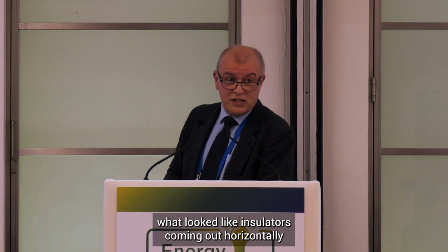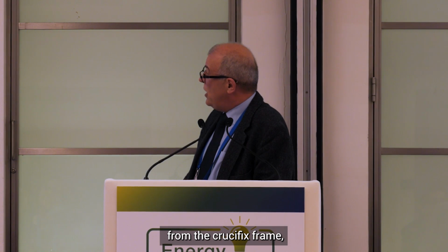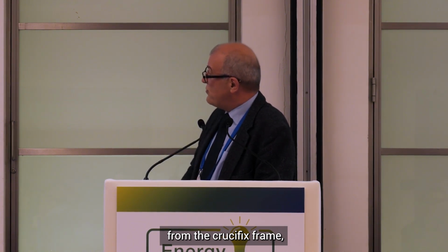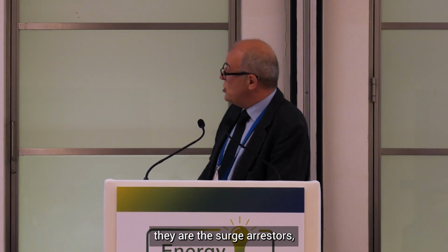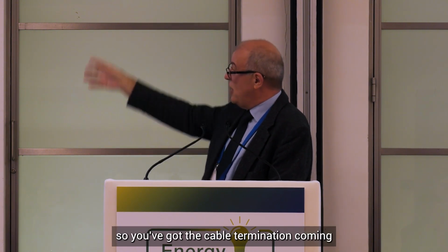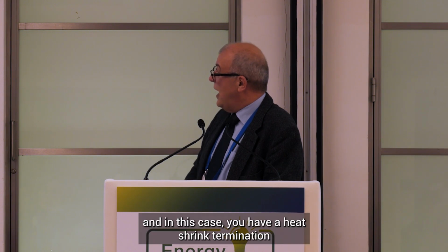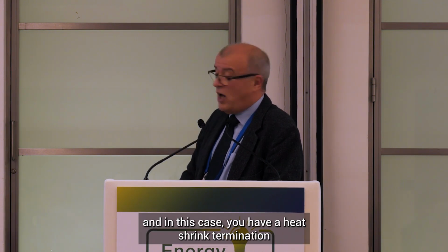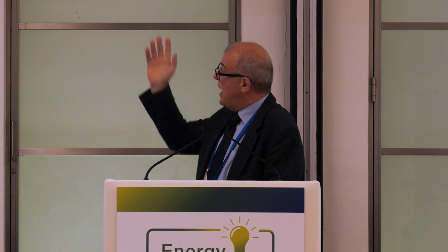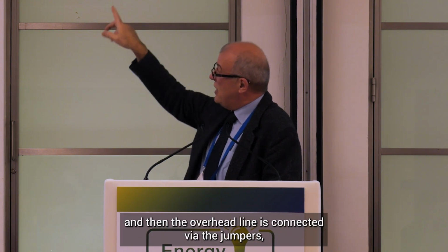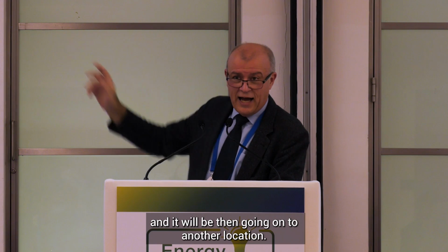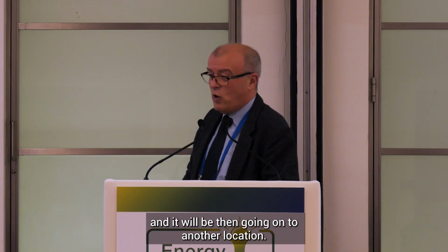what look like insulators coming out horizontally from the crucifix frame, they are the surge diverters. So you've got the cable termination coming up from below, and in this case you have a heat shrink termination, and then the overhead line is connected via the jumpers, and it will be then going on to another location.